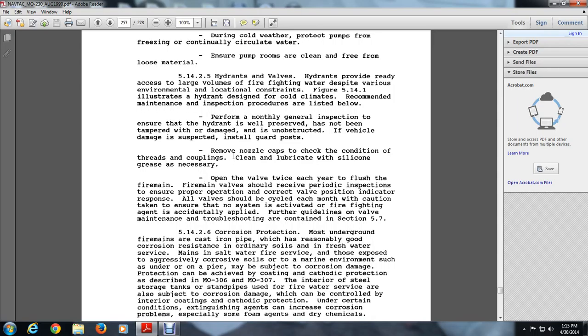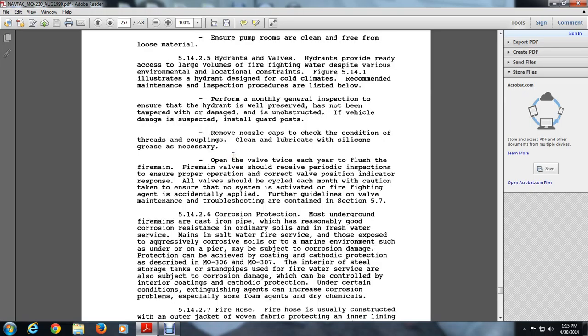5.14.2.6 Corrosion protection. Most underground fire mains are cast iron pipes and must be reasonably resistant to corrosion in ordinary soils and freshwater services. Saltwater fire service mains exposed to aggressively corrosive soils in the marine environment, and those under or on the pier, may be subject to corrosion damage. Protection can be achieved with coatings and cathodic protection described in 306 and 307.